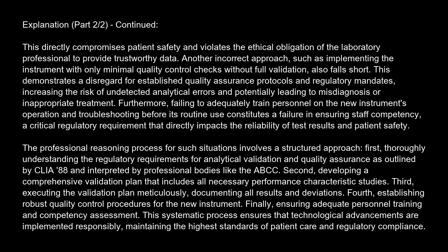Third, executing the validation plan meticulously, documenting all results and deviations. Fourth, establishing robust quality control procedures for the new instrument. Finally, ensuring adequate personnel training and competency assessment. This systematic process ensures that technological advancements are implemented responsibly, maintaining the highest standards of patient care and regulatory compliance.